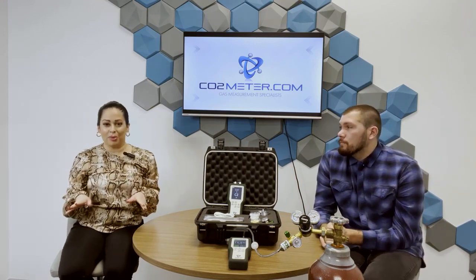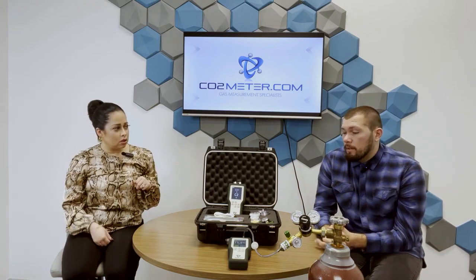To reiterate, annual calibration is typically recommended for this device, but can CO2Meter provide both of those calibration methods in-house? Yeah, in-house we will absolutely calibrate the entire device, all 4 sensors in one swoop.